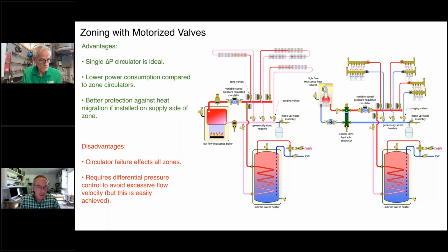And for years, I've been a strong proponent of putting zone valves on the supply side of the circuits. I know there are systems out there where they're on the return side. The advantage of putting them on the supply side is that they are a good blocking device for heat migration. And keep in mind that you can have 2-directional flow in a single pipe. If we were to remove this valve, hot water will actually go up through the center of that pipe. And then along the internal walls of the pipe, the heat transfer will cool that water, and you'll actually get a slight heat migration effect.